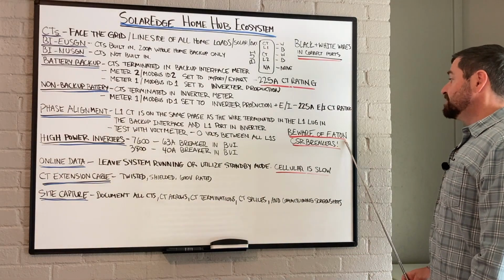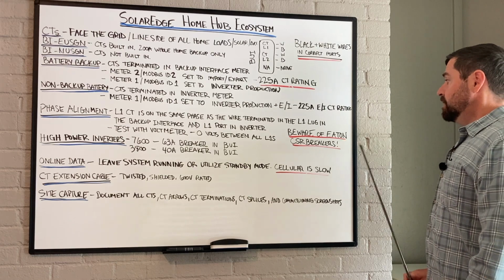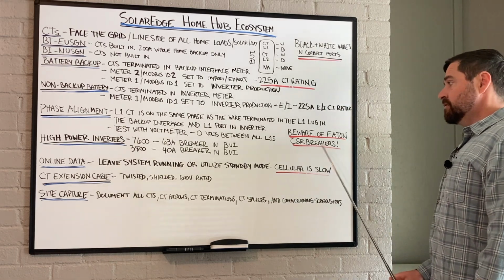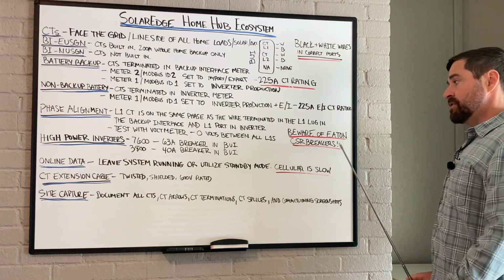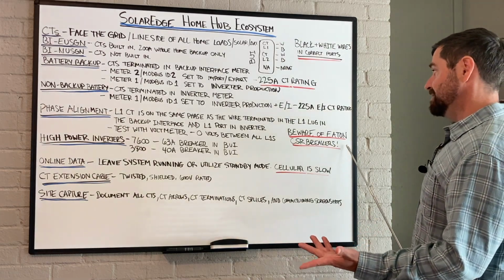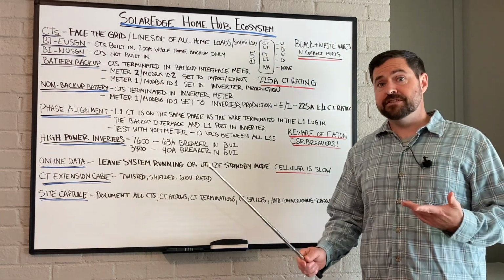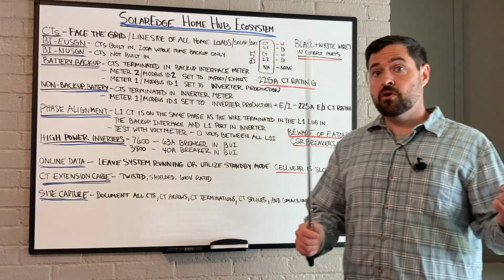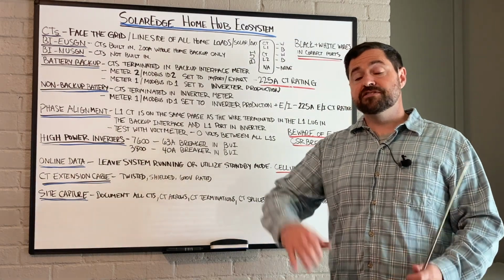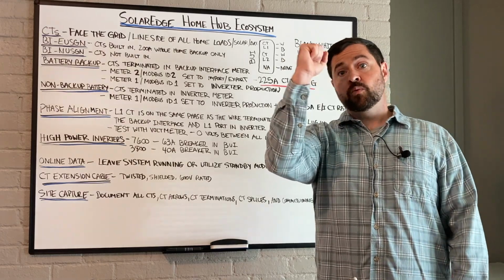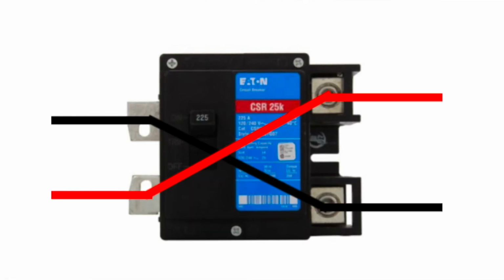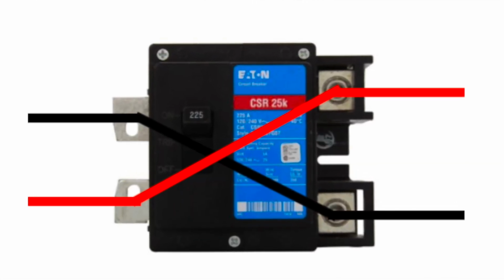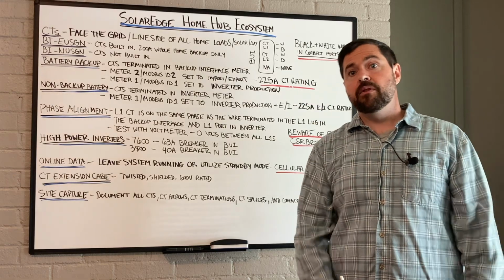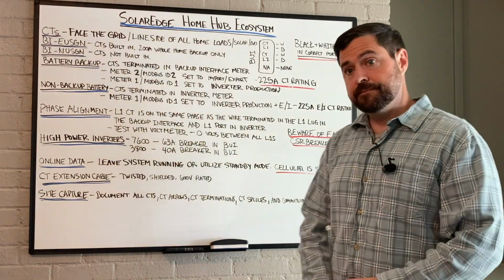Beware of Eaton CSR breakers. These are commonly used in many other manufacturers' equipment. For SolarEdge, you don't really have to worry about it unless they're installed in a main service panel somewhere. Those cross phases inside the breaker. So L1 on one side of the breaker is going to be the opposite on the opposite side of the breaker. So you can really get swished around there if you don't test with a voltmeter.